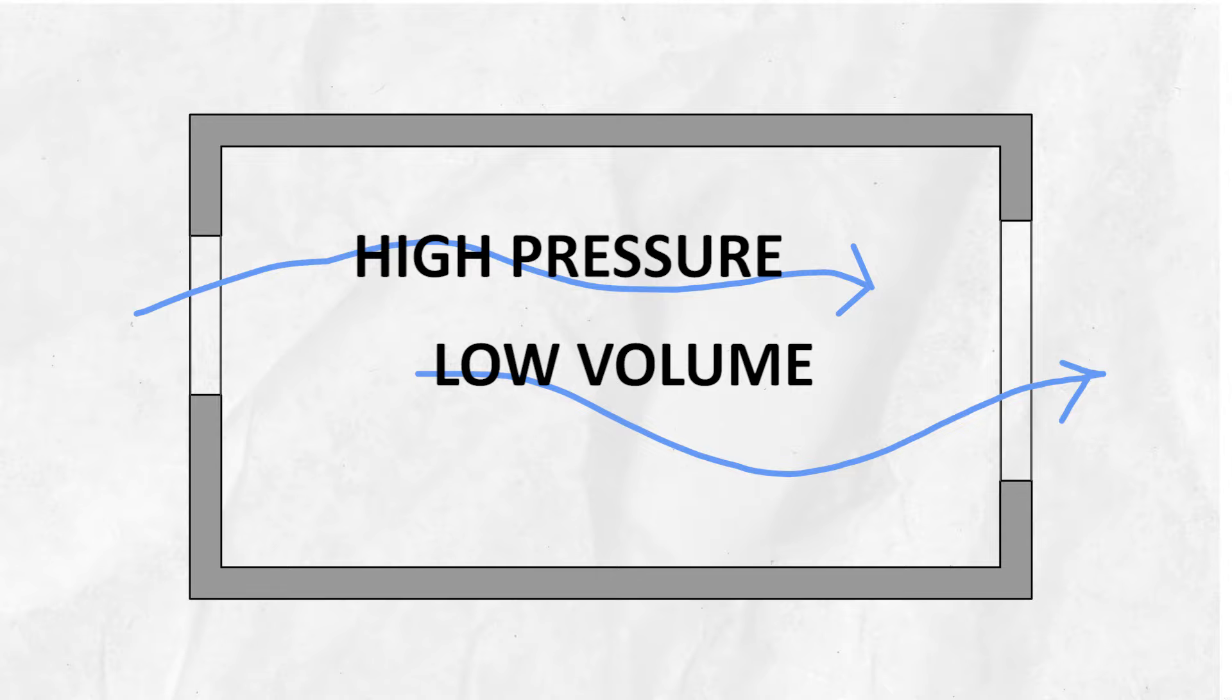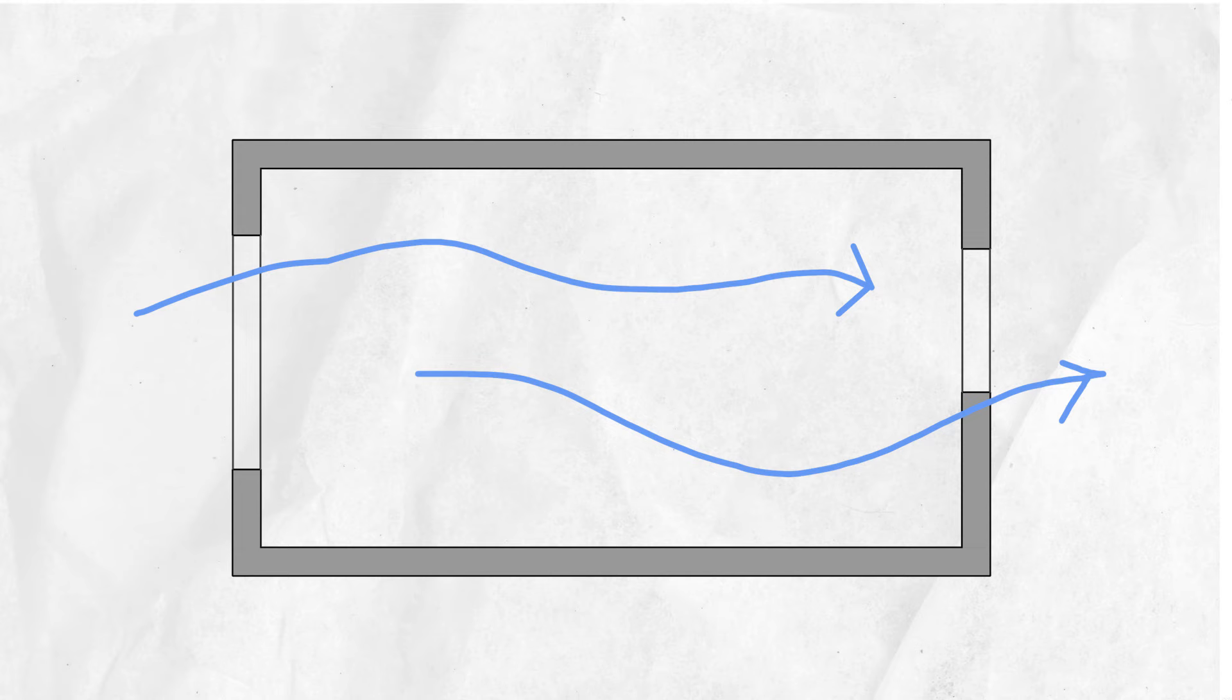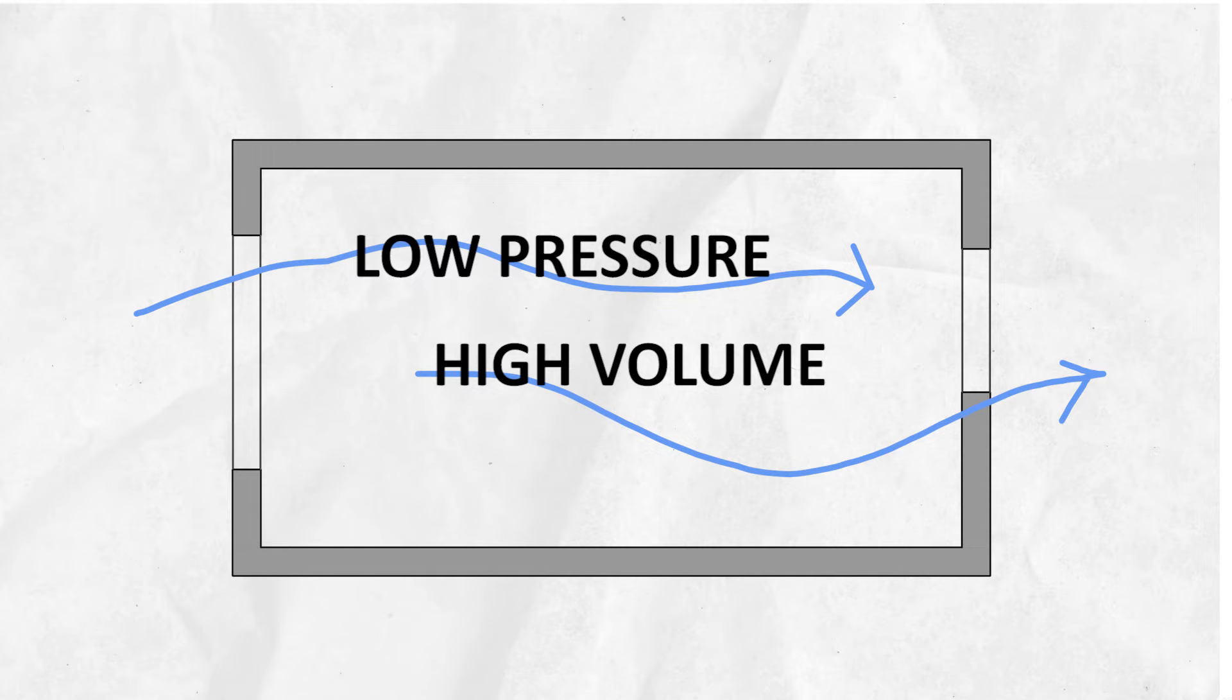When the inlet opening is large, the air velocity through it will be less, but the volume of air passing will be higher. When wind direction is not constant or when airflow through the whole space is required, a larger opening will be preferable.